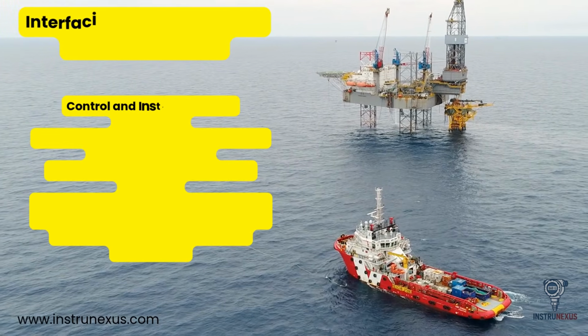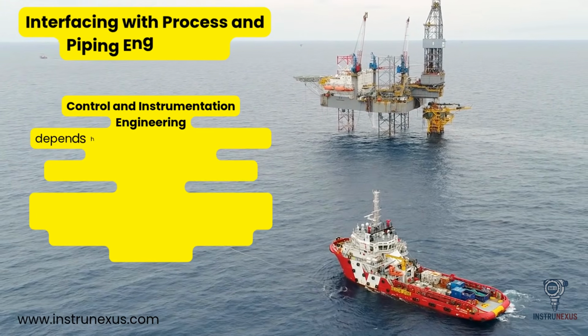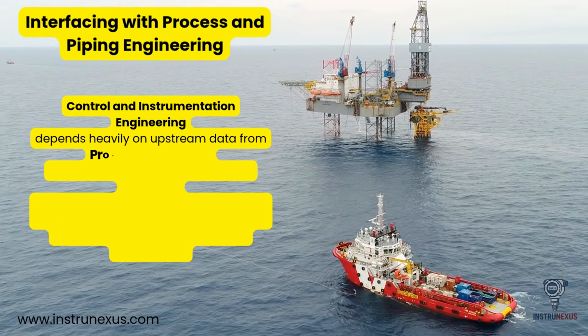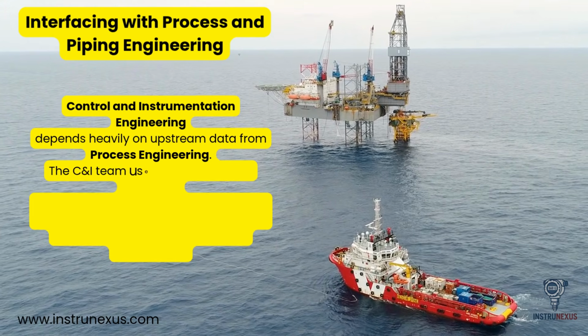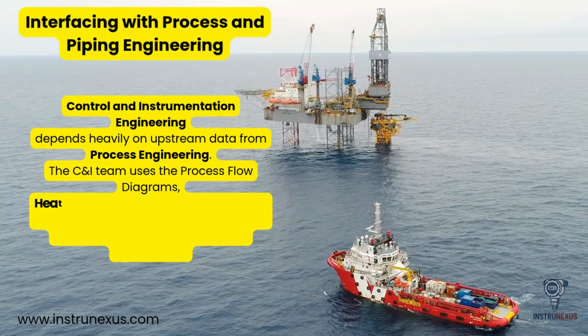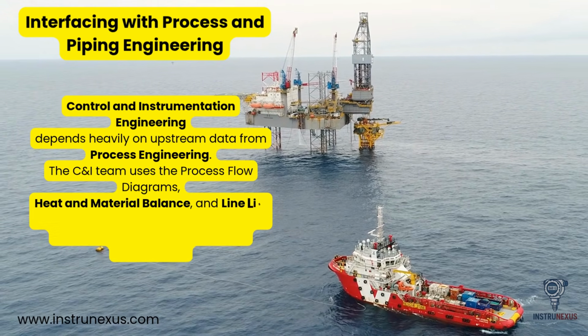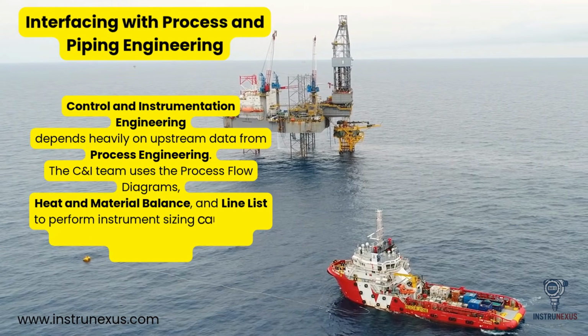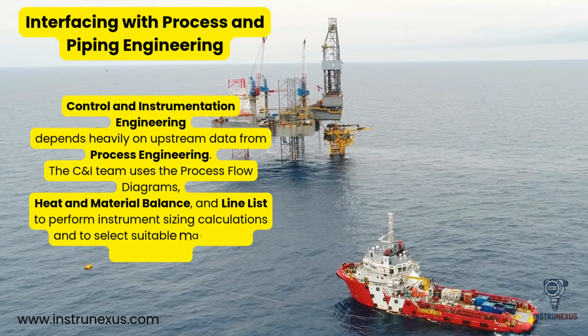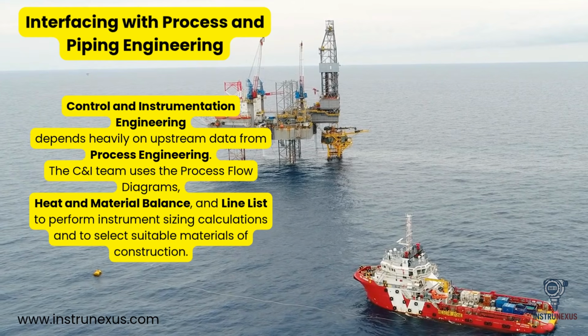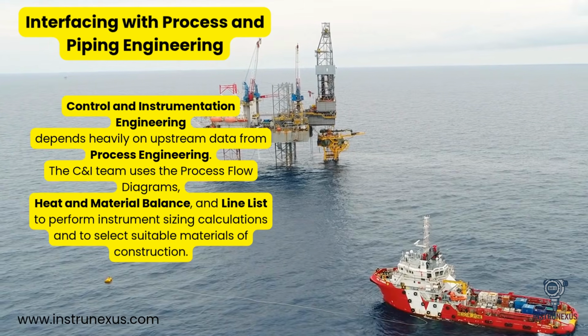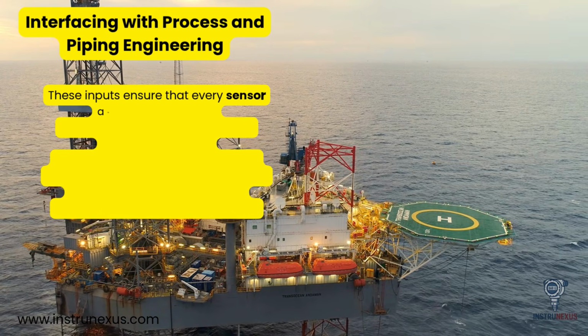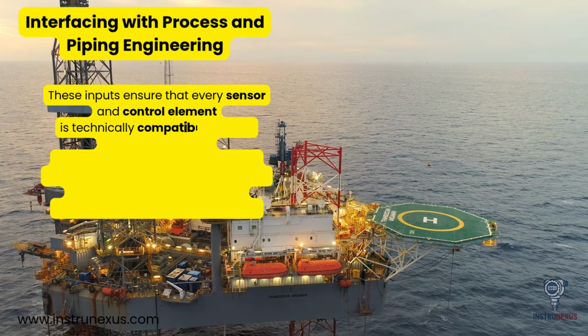Control and instrumentation engineering depends heavily on upstream data from process engineering. The C&I team uses the process flow diagrams, heat and material balance, and line list to perform instrument sizing calculations and to select suitable materials of construction. These inputs ensure that every sensor and control element is technically compatible with the process conditions.